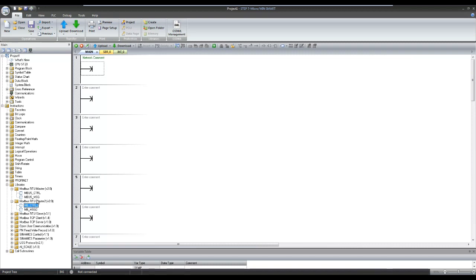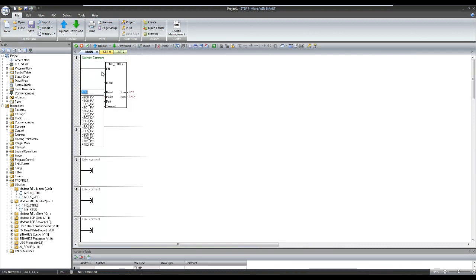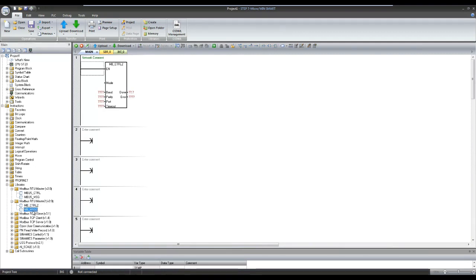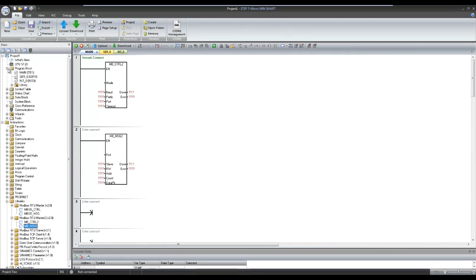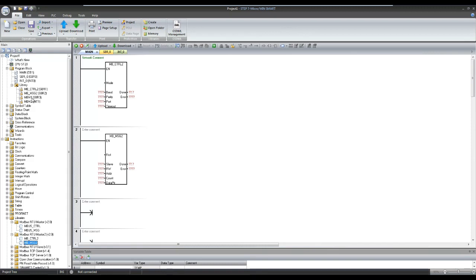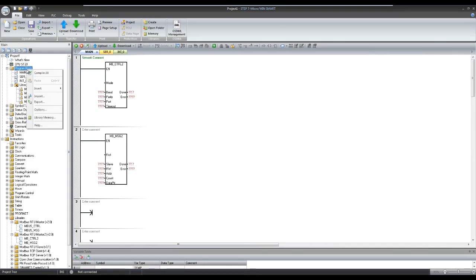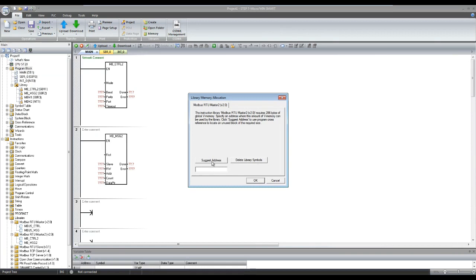You can simply drag and drop these blocks to your work area. Once you use these blocks in your program, these new subroutines will be automatically created under the library section in the programming block. These subroutines require certain memory allocation to execute the instruction written inside the blocks. So for this we will be required to allocate the V memory areas for these blocks. Note that this memory area should not be overlapped with your existing memory usage or with any other libraries that you are using in a program.